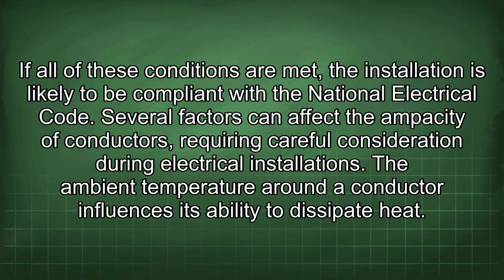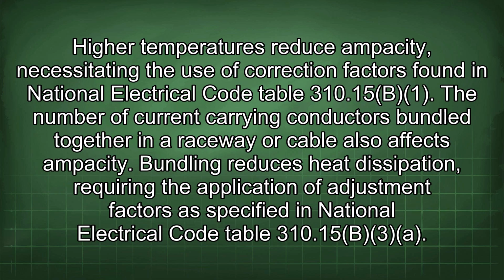Several factors can affect the ampacity of conductors, requiring careful consideration during electrical installations. The ambient temperature around a conductor influences its ability to dissipate heat. Higher temperatures reduce ampacity, necessitating the use of correction factors found in National Electrical Code Table 310.15(B)(1).